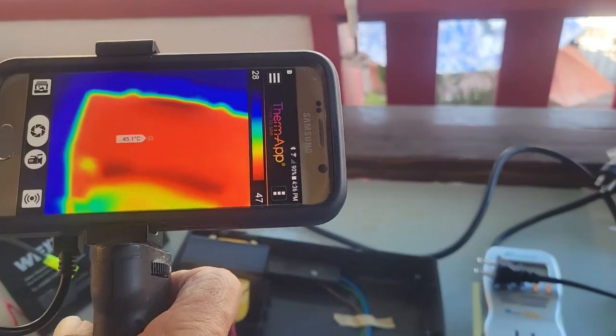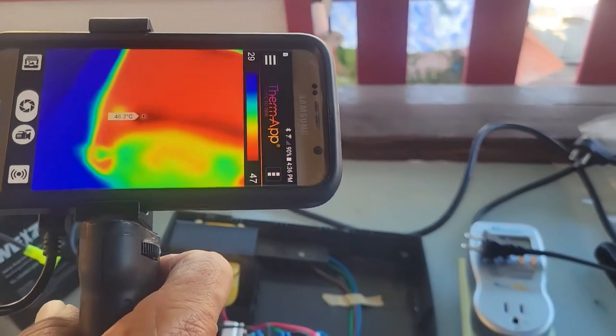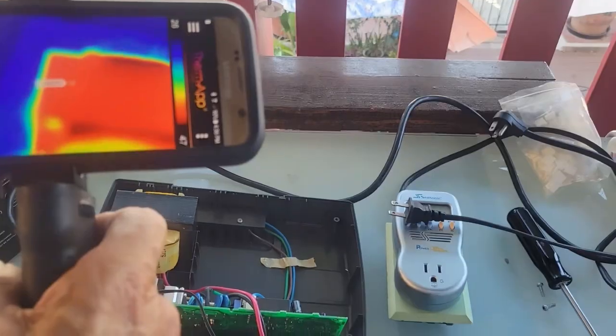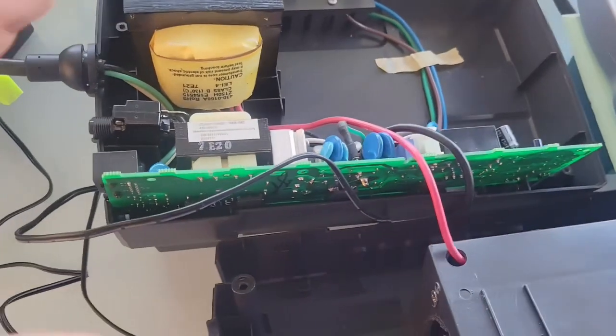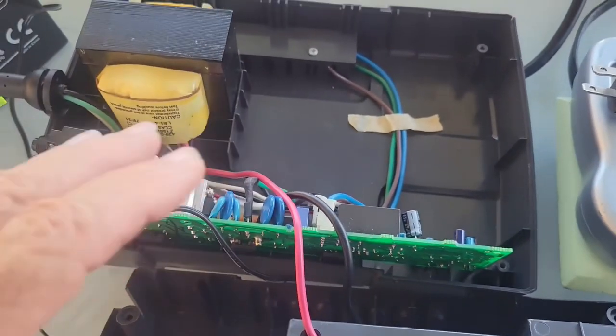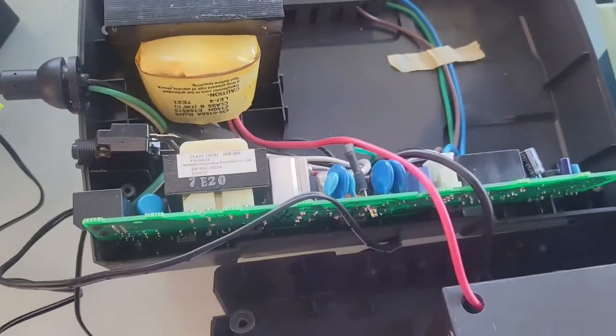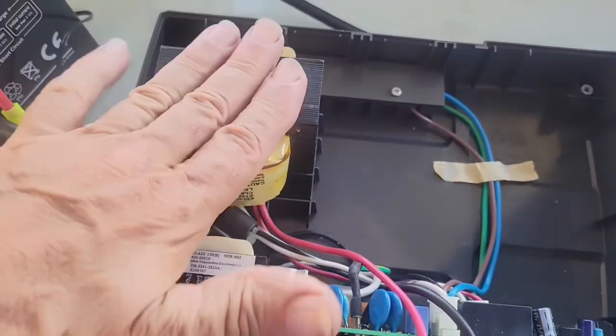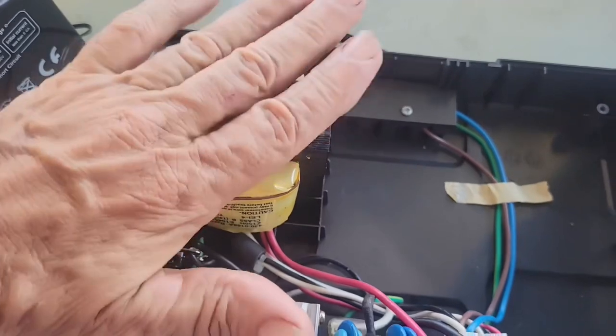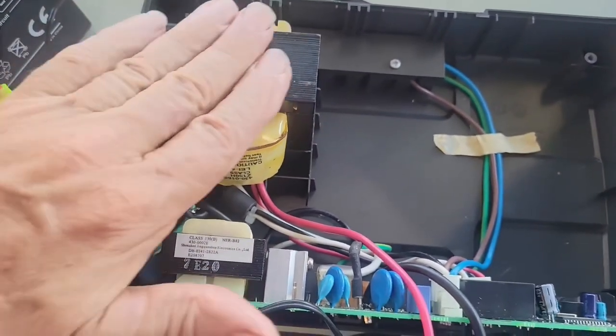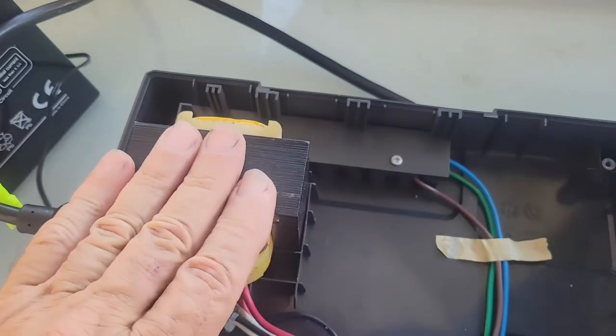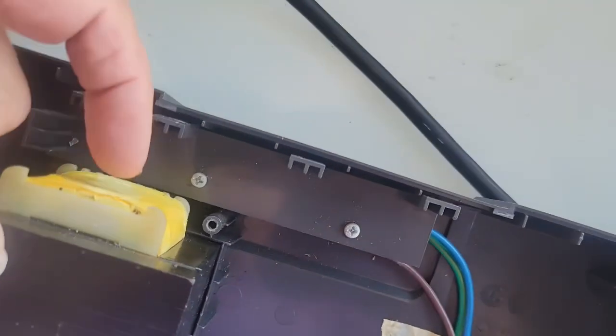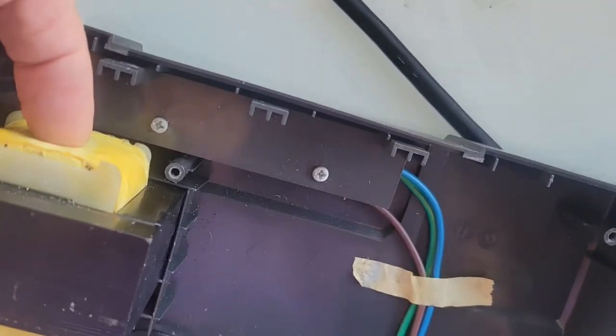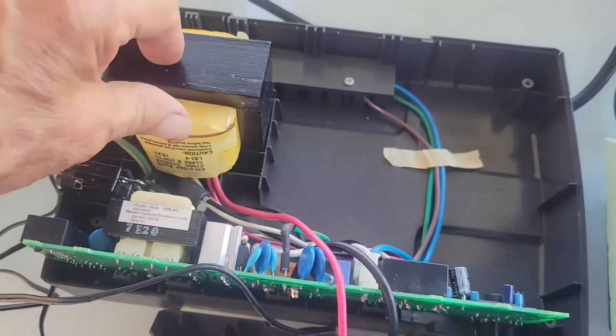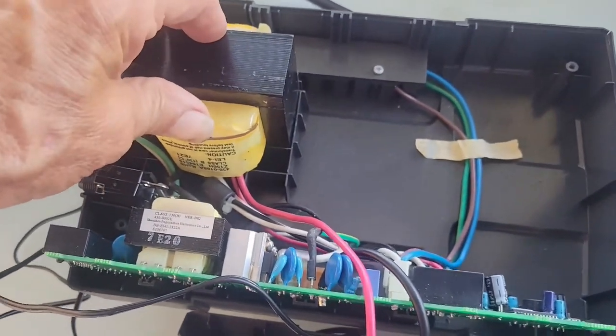I'm going to put the camera down so I can get a temperature reading here. Of course, as soon as I took it apart, it's already on the cool down, but I immediately put my hand on it, and it's not bad. So the reading I got from the thermal camera, the hottest temperature was actually on this side of the transformer, and it was about 50 degrees C.